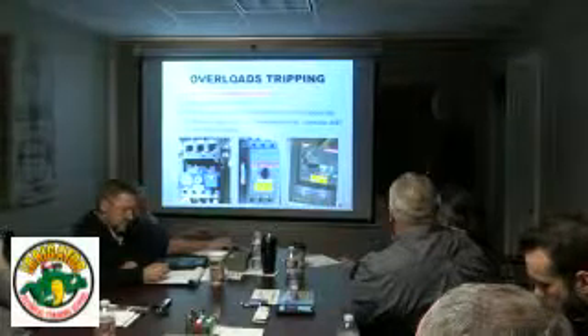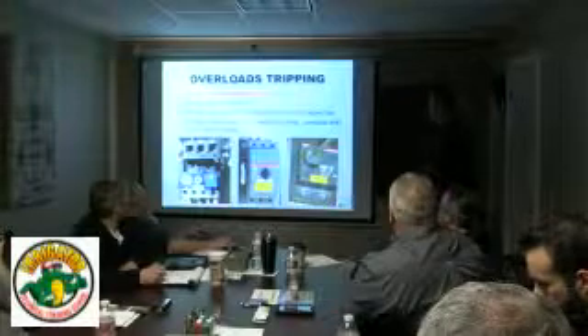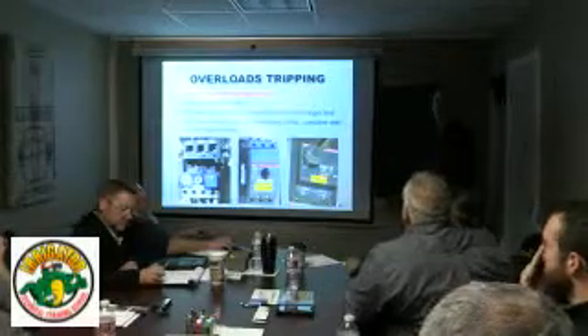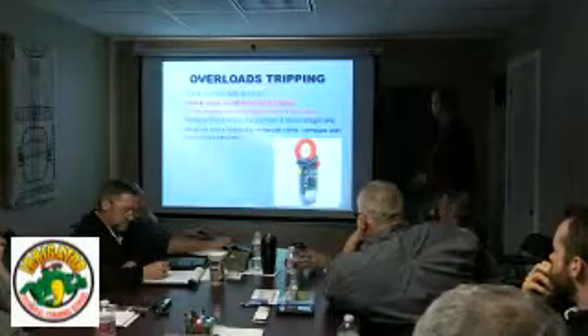In this case, it's on the input of a drive. It could be that one of the input diodes of the drive's bad. Most cases, I would just turn the power off, reset it, close the door, turn the power back on, and see if it trips again. Well, let's go back to this one.